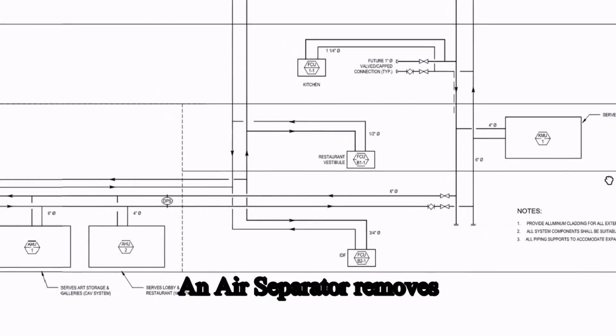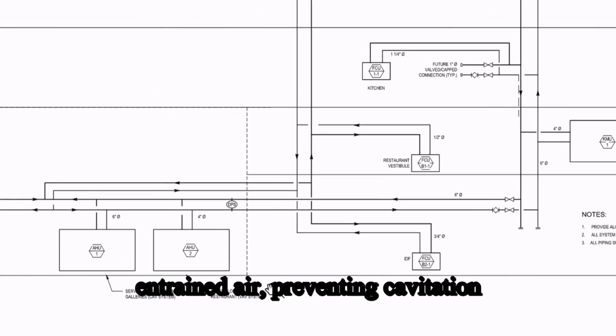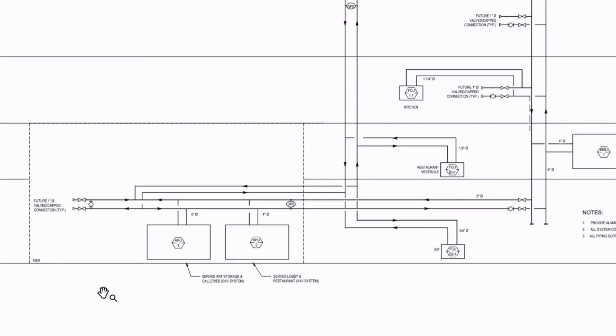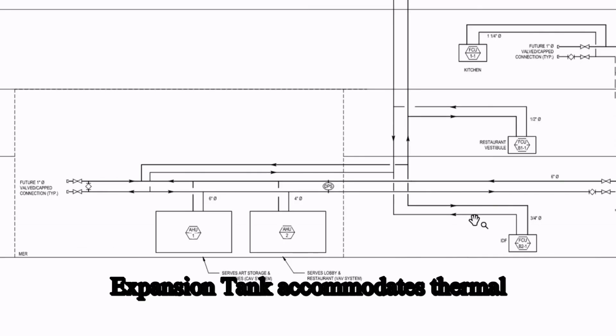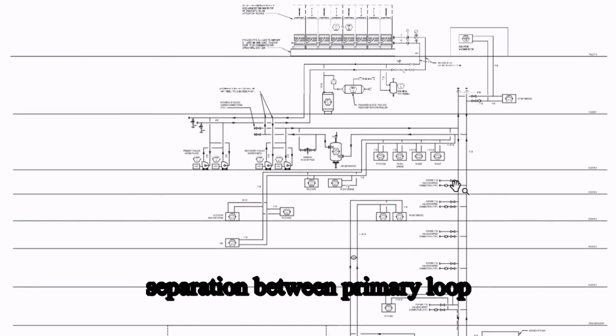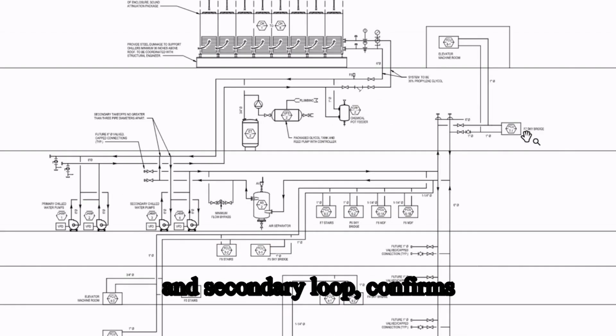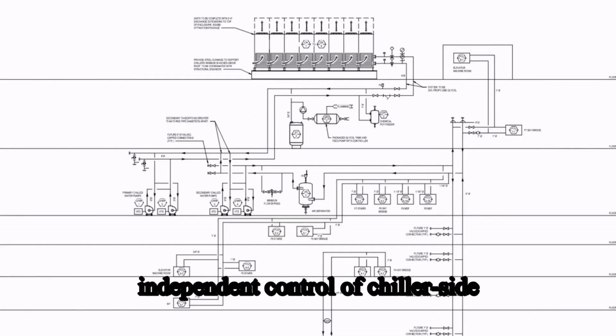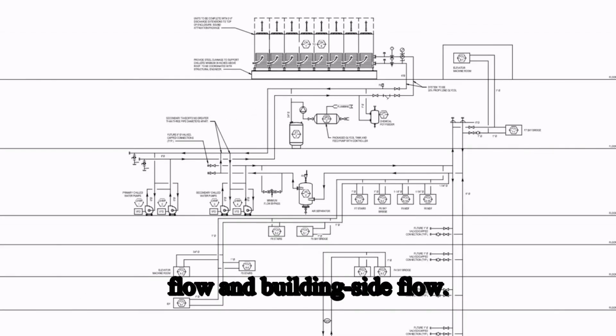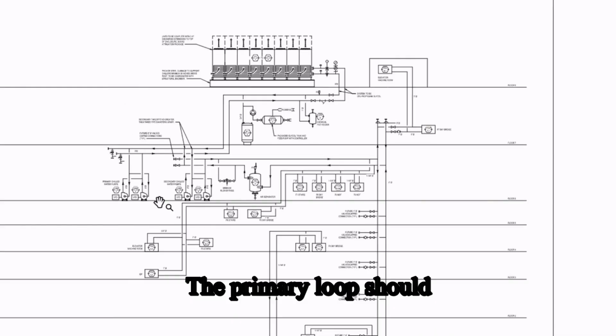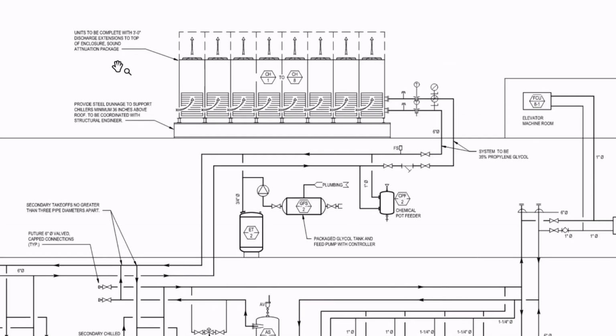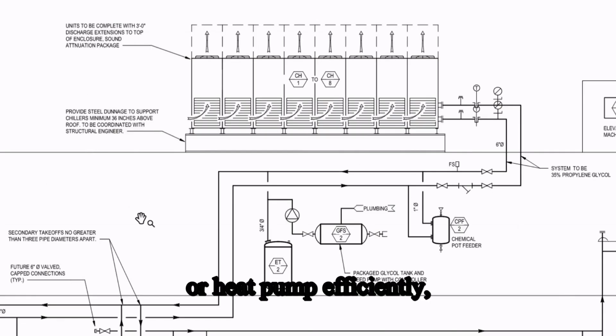An air separator removes entrained air, preventing cavitation and corrosion. The expansion tank accommodates thermal expansion of the glycol mix. The decoupler maintains hydraulic separation between the primary loop and secondary loop, ensuring independent control of chiller side flow and building side flow. The primary loop should have enough water volume to run the chiller or heat pump efficiently.